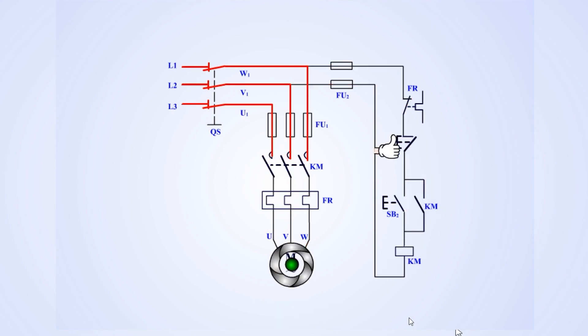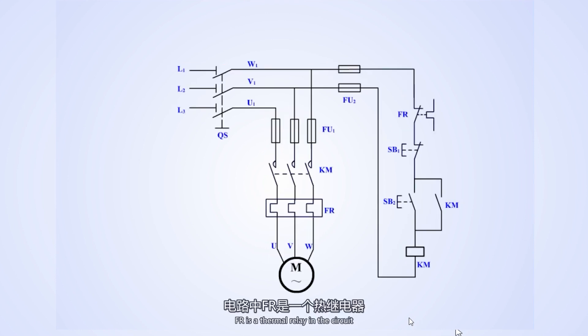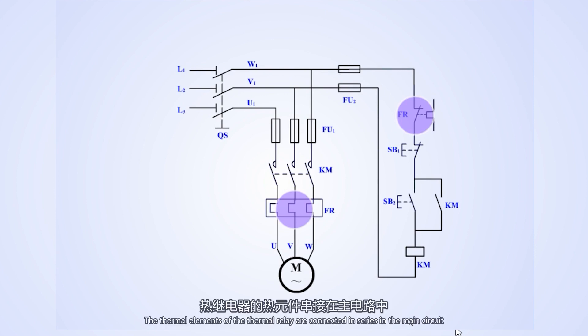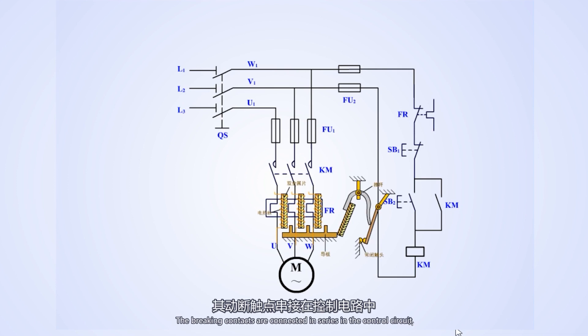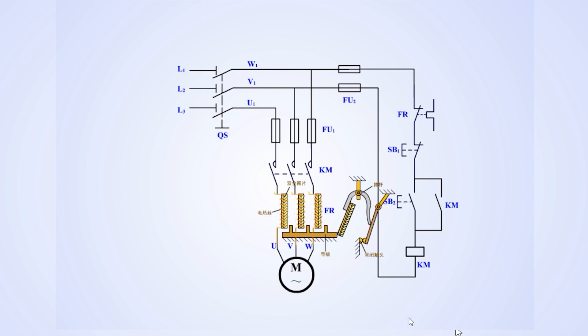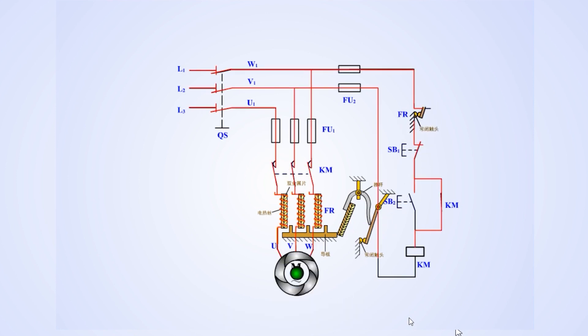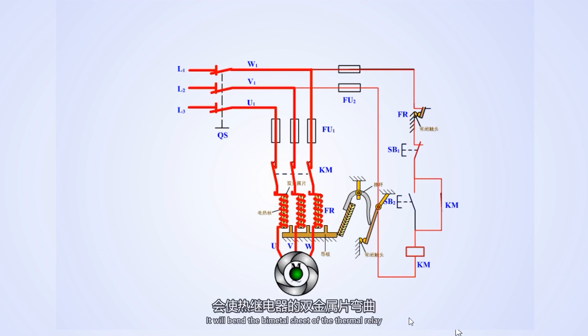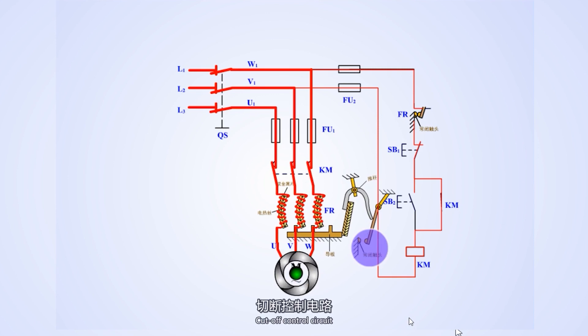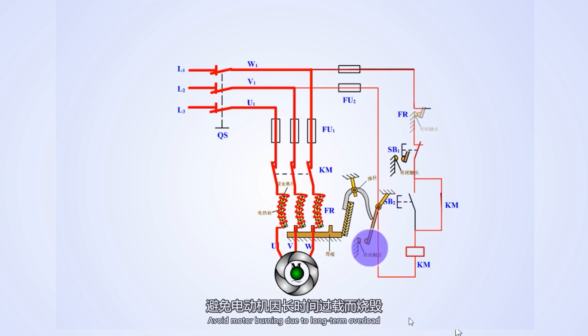To stop the motor, just press SB1. FR is the thermal relay in the circuit, which protects the motor from overload. The thermal elements of the thermal relay are connected in series in the main circuit, and the breaking contacts are connected in series in the control circuit. When an overload failure occurs, the current in the motor winding will greatly increase, exceeding the rating. The excess heat will bend the bimetal sheet of the thermal relay, pushing its breaking contact to disconnect, cutting off the control circuit, and avoiding motor burnout due to long-term overload.